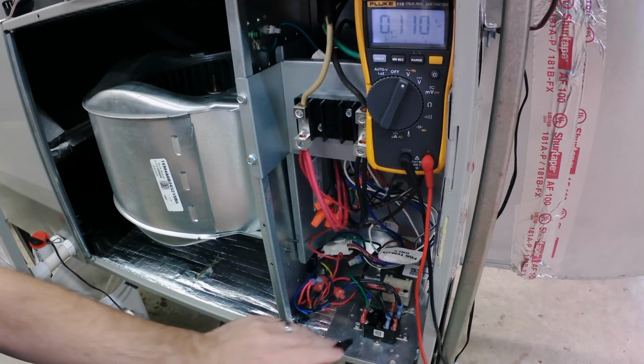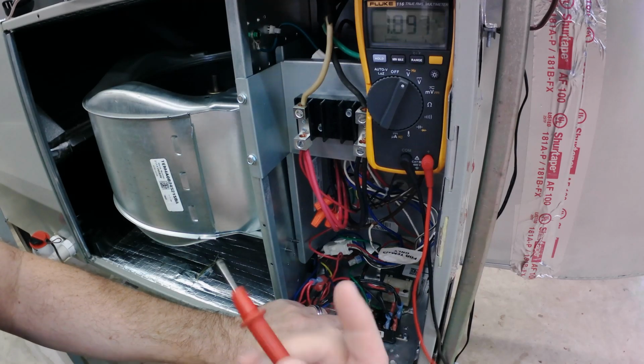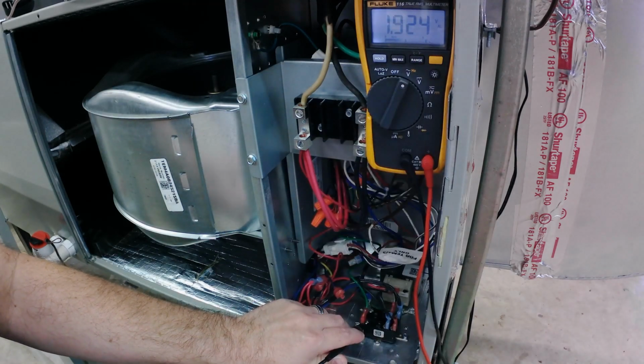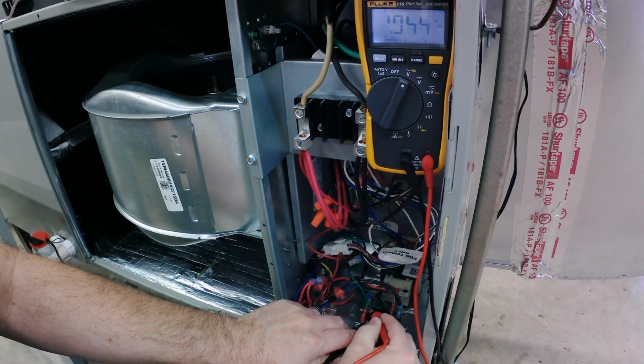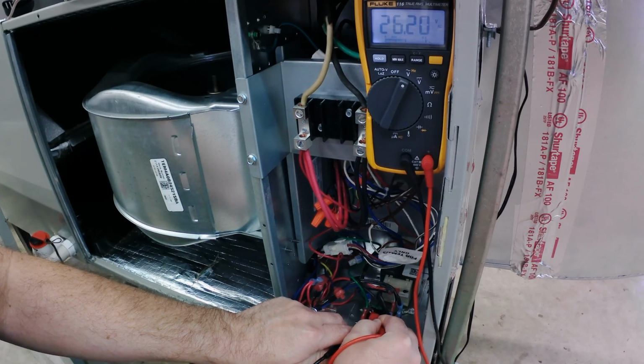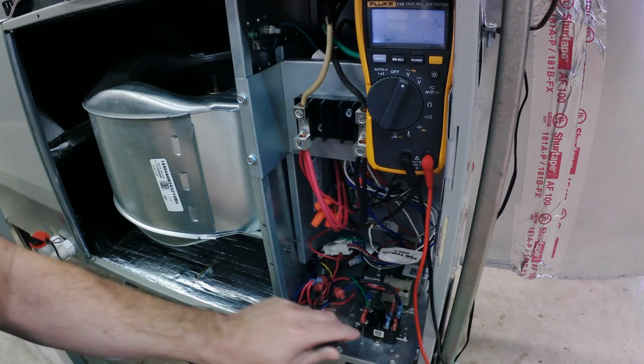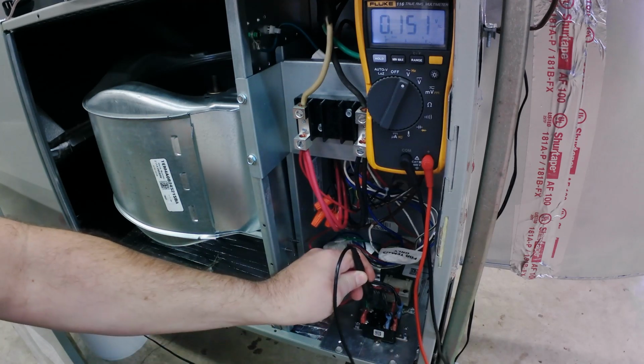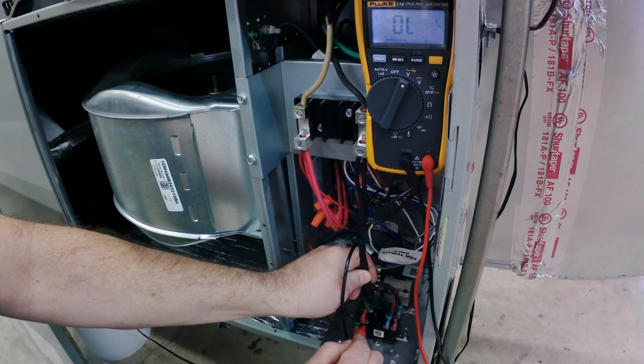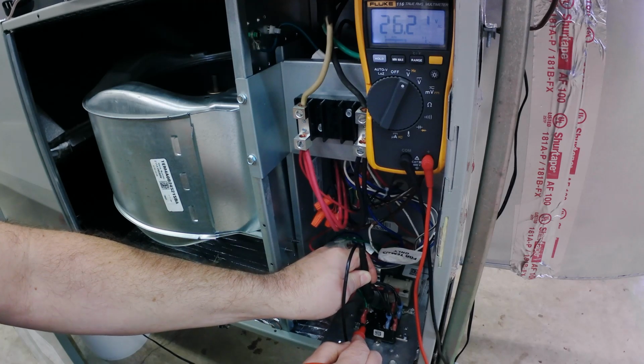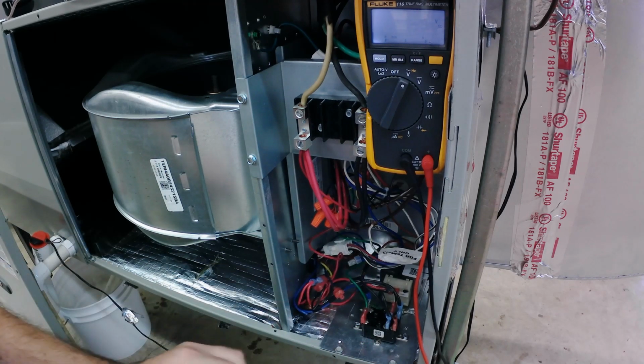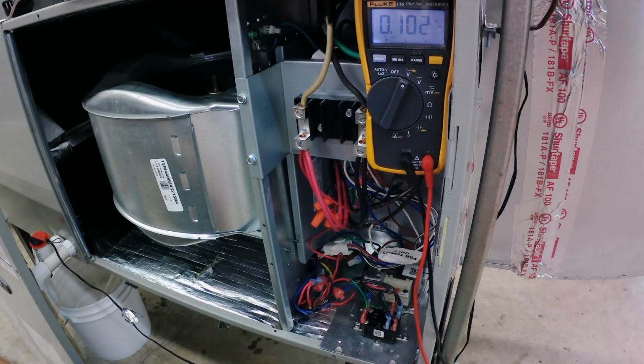And I think there's a slight delay in the thermostat, right? So what I'm doing now is I'll do the same check on the coil, and you can see I've got 26 volts. So from the common to the coil, the G to the C, right, is 26 volts. That means that coil is getting power from the thermostat.